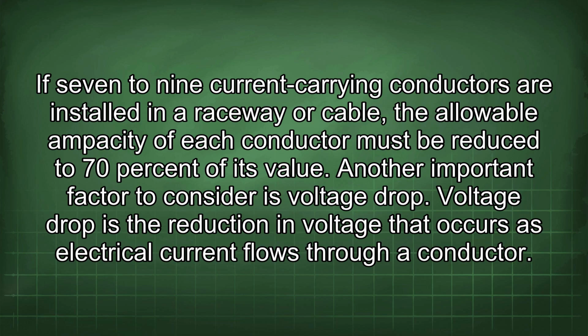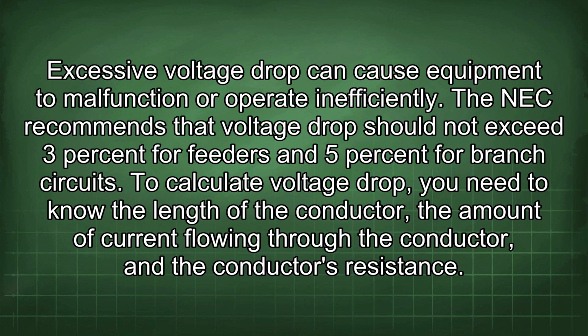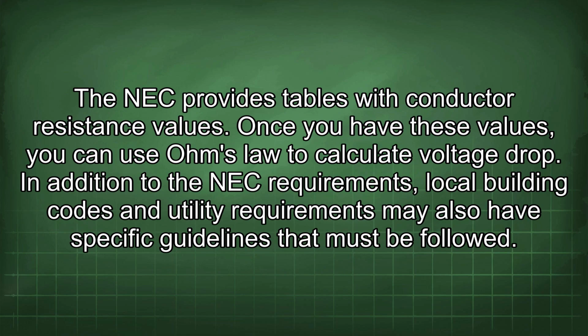Another important factor to consider is voltage drop. Voltage drop is the reduction in voltage that occurs as electrical current flows through a conductor. Excessive voltage drop can cause equipment to malfunction or operate inefficiently. The NEC recommends that voltage drop should not exceed 3% for feeders and 5% for branch circuits. To calculate voltage drop, you need to know the length of the conductor, the amount of current flowing through the conductor, and the conductor's resistance. The NEC provides tables with conductor resistance values. Once you have these values, you can use Ohm's law to calculate voltage drop. In addition to the NEC requirements, local building codes and utility requirements may also have specific guidelines that must be followed.